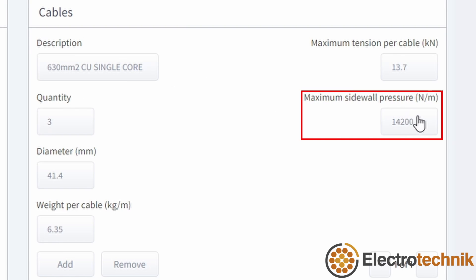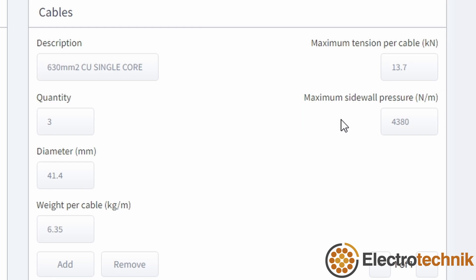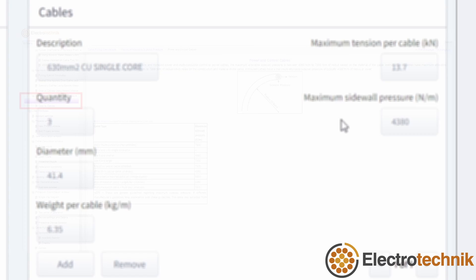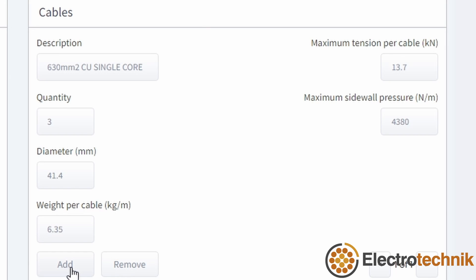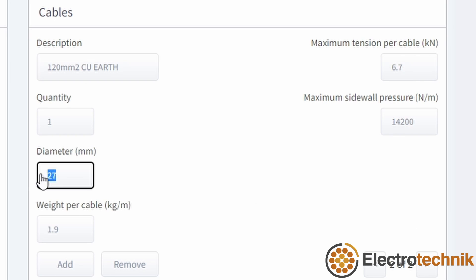The sidewall pressure is the radial force exerted on a cable at a bend point when the cable is under tension. The value for maximum sidewall pressure, also called maximum sidewall bearing pressure, can be harder to get from the manufacturer or cable datasheet, but it is important unless there are no bends in your cable pull. There is a section in the help manual called maximum allowable sidewall pressure which provides standard values if you can't get it from the manufacturer. To add another cable type to the pull, press add, then use the arrows to move between cable types. Make sure you enter the total number of cables for each cable type under quantity.